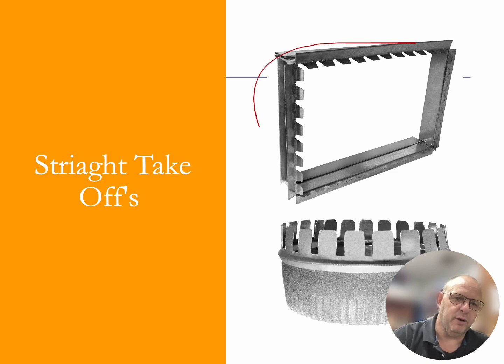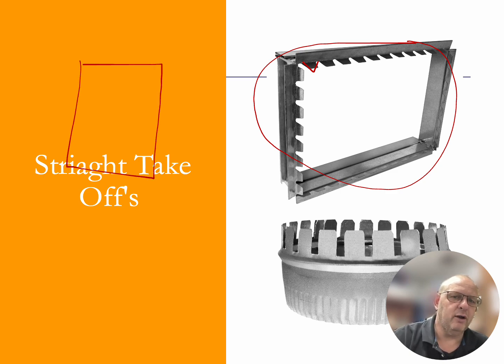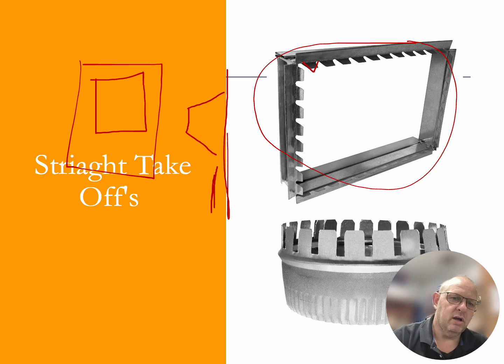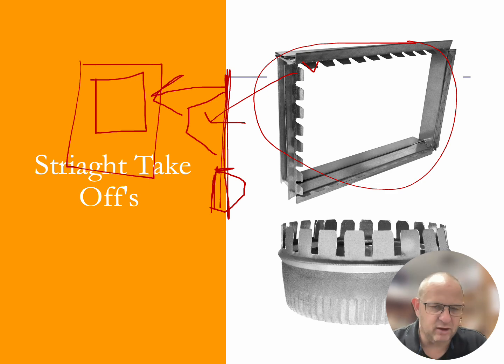Now, this individual component right here is a takeoff. You see the feet that are on this. What we will do is inside of the plenum, we will cut a hole in the dimension of this takeoff. Now, when we put this takeoff in, these little ribs that are on the takeoff are going to look like this, and we're going to take them and bend them over the metal that's inside of that takeoff right there. So these little ribs are indicated right there. This is the metal, and then we'll take it and we'll bend it over that metal that's sitting on it, so that we can make a nice seal on that.